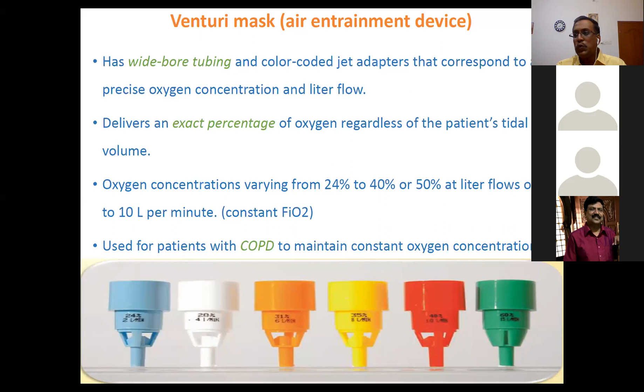This device delivers a fixed concentration of oxygen to the patient by Bernoulli's effect and the Venturi principle. Here there is a driving fluid A, that is, gas passing through this wide-bore cannula which has an abrupt narrow ending. The driving pressure of fluid A will be drastically reduced when it reaches the narrow compartment, and the pressure there becomes very low, less than atmospheric, subatmospheric. It will draw air from the environment, which mixes with the oxygen, and the mixture is very constant and delivers a fixed concentration of oxygen to the patient. That is Bernoulli's effect and the Venturi principle.